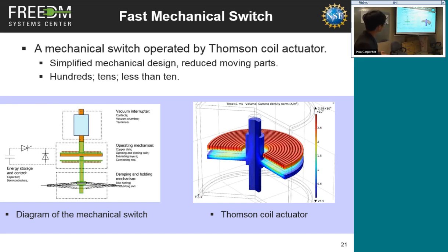We have this Thomson coil, and we need some circuit to drive it, and we need to translate this movement to the contact. We use the vacuum interrupter here as the dielectric and also as the contact. The contact sits inside the vacuum interrupter in the vacuum environment, and there's a shaft connecting this moving part, the movable contact, our actuator, and also some mechanism here. This mechanism is used for damping and holding the movable contact in the open and closed position.